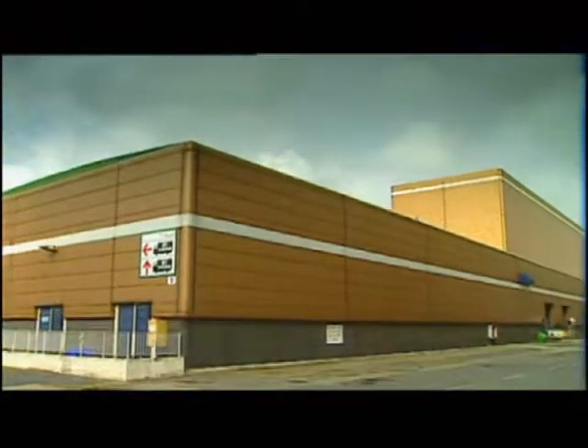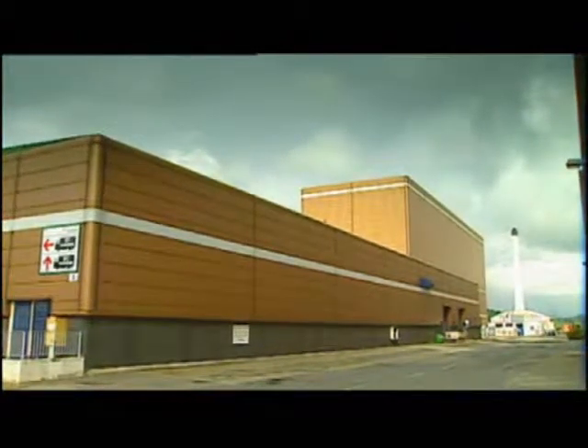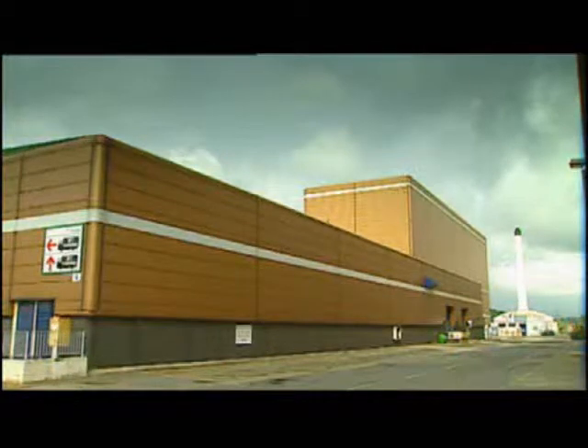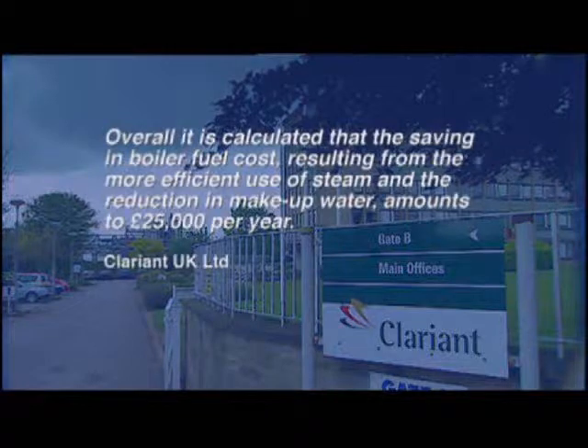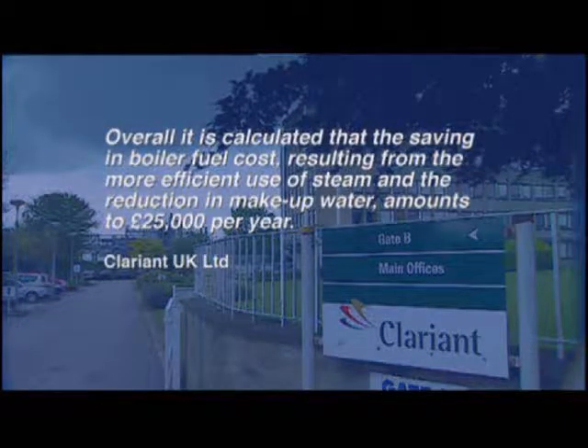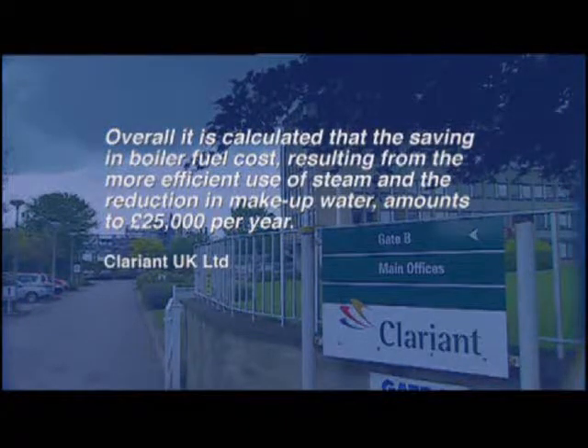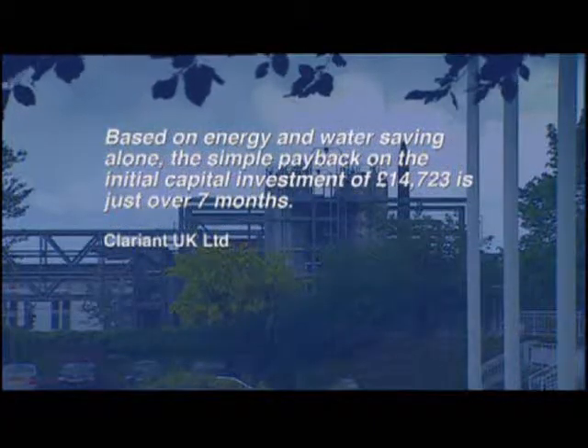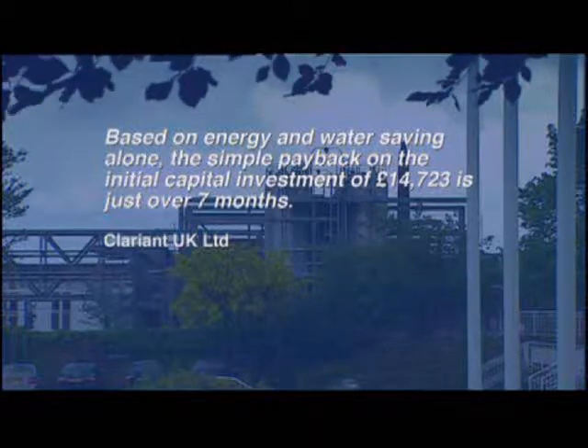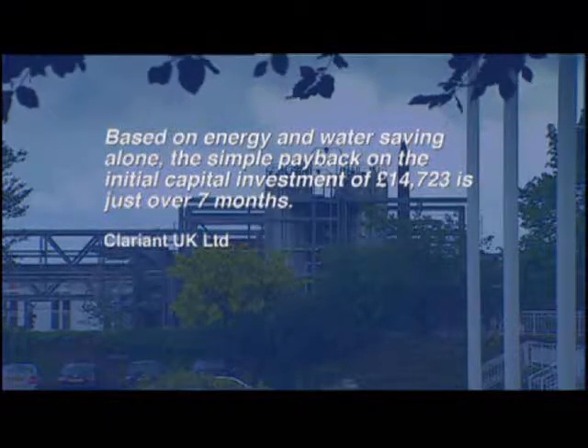Multinationals like chemical giant Clariant, who installed 73 traps across a variety of applications, have seen operational improvements as well as savings. Overall, it's calculated that the saving in boiler fuel cost resulting from the more efficient use of steam and the reduction in make-up water amounts to £25,000 per year. Based on energy and water saving alone, the simple payback on the initial capital investment of £14,723 is just over seven months.